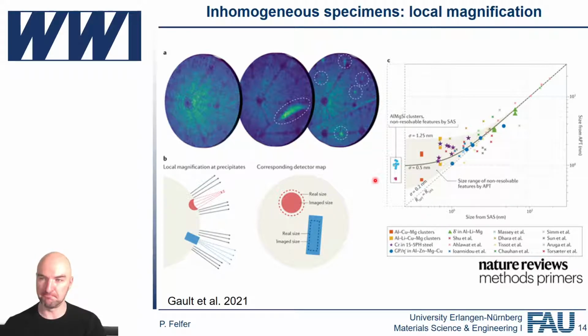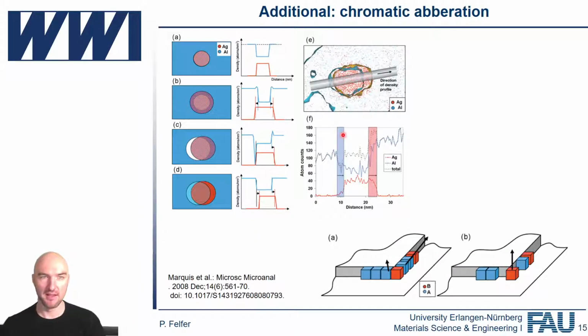It's something that we can work on with the reconstruction, because this is mostly an artifact that preserves the neighborhood relationships between atoms. They can get broken if it's an extreme case, but for the most part, neighborhood relationships are preserved. Here, neighborhood relationships are broken, but not by a massive amount, maybe a nanometer or two. So as long as you don't start looking at which atomic plane stuff sits in, you're going to be all right.